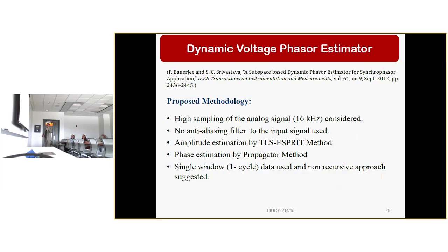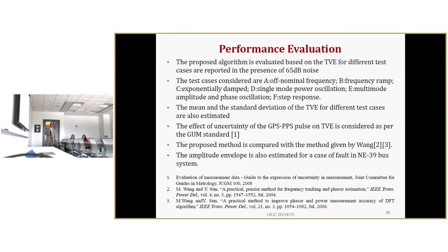The first work which we did was on dynamic voltage phasor estimation. I'll not go into the mathematics, but give you some idea. We have used a combination of TLS-ESPRIT, total least square estimation of signal parameters through rotational invariance technique, and a propagator method. These are very well known signal processing techniques. We found that this gives good accuracy of amplitude estimation. The other one gives good accuracy for phase estimation. A single data window we have used, and the approach we gave was non-recursive, so it is faster. This was published in IEEE Transactions on Instrumentation and Measurement. Then we tested for various conditions, and we also tested for uncertainty defined in the GUM standard and compared with some of the adaptive DFT based methods.